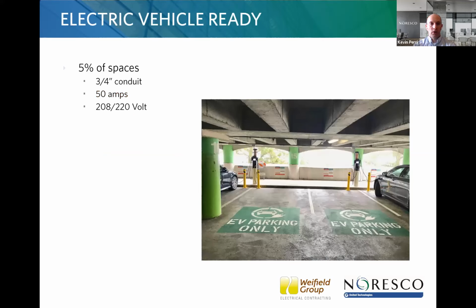Jim, I'll turn it over to you for the electrical side. Okay, so Fort Collins does have electrical vehicle ready requirements. It's 5% of the spaces, but it's an empty 3/4 inch conduit for a 50 amp circuit. However, in Fort Collins, it has to come from a panel with breaker space and so on in it. So in Fort Collins, you will have to build out the electrical infrastructure to provide EV power to 5% of the spaces in the city of Fort Collins. Next, Kev.